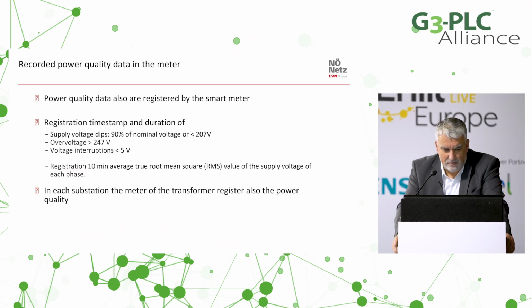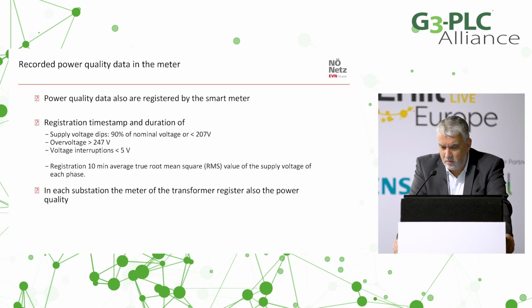The next step is now to use the power quality data which will be registered by the smart meter. On one side we register the timestamp and duration of supply voltage dips when the voltage is below 90%, or 207 volts. Overvoltage is more than 247 volts. It's not plus 10%, it's less. So we have room to see when the voltage gets too high when too much PV is installed in this low voltage grid, and we also register all voltage interruptions below 5 volts. It is a requirement of the Austrian regulator.